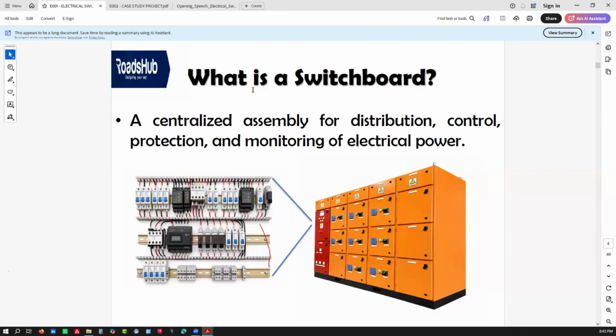So I tried to expand what was inside that panel. What you can see is actually a changeover control system. The image on the left is a discrete component control system that can switch between two sources by controlling a circuit breaker. In this case, I'm talking about an air circuit breaker.